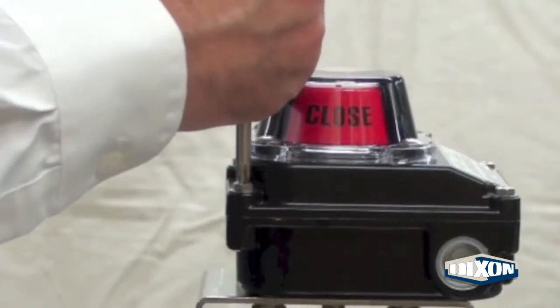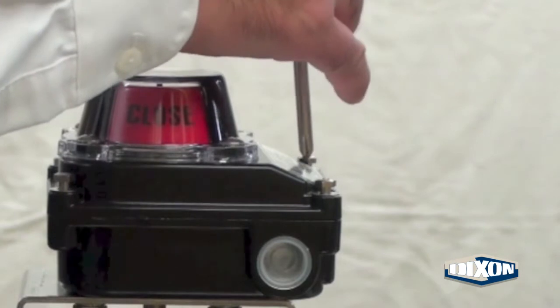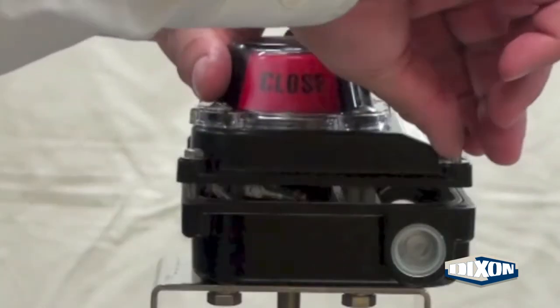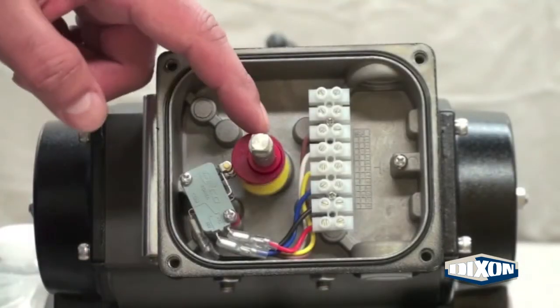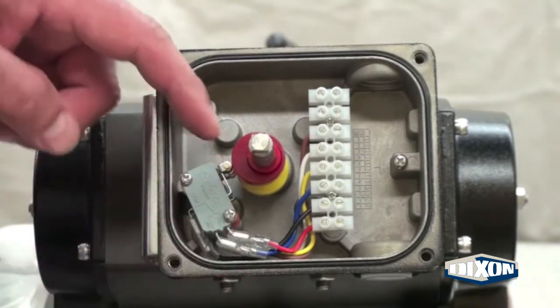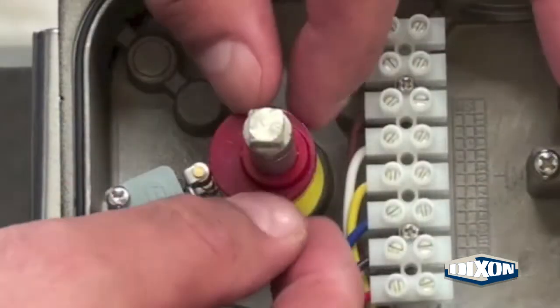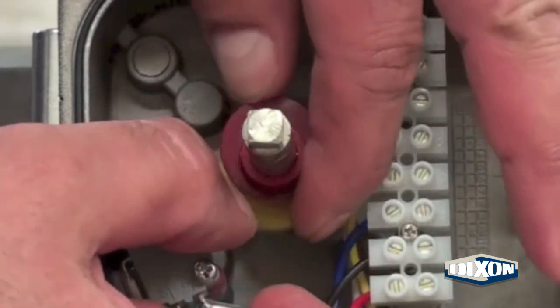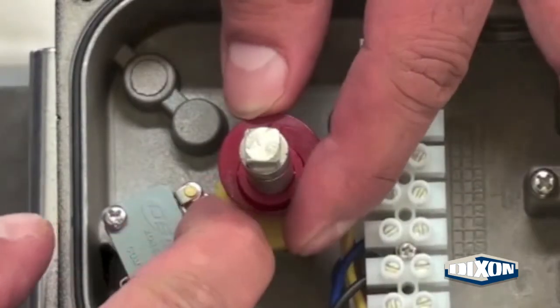Back out the captive cover bolts on the limit switch box. Carefully lift off the cover of the limit switch. Set the cams inside the limit switch box so that they depress the micro switches. Push down on the cam so it clears the splines, rotate and release.